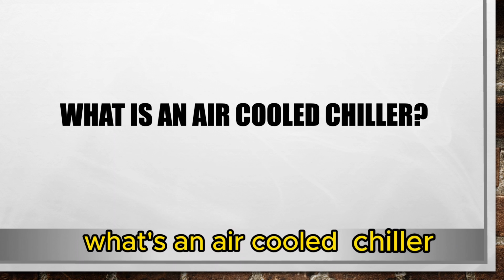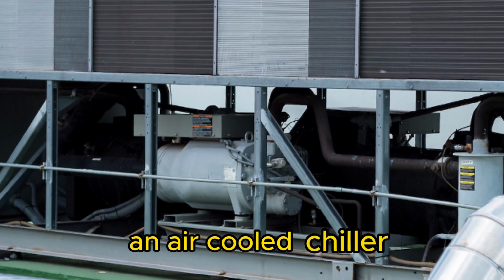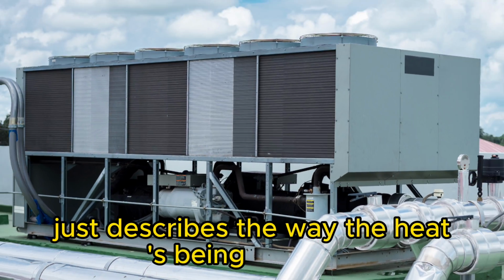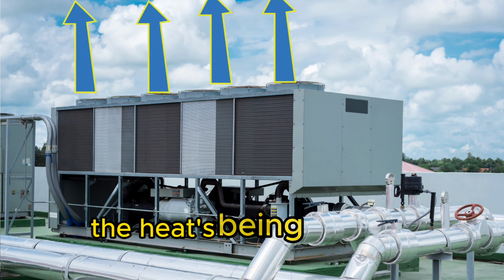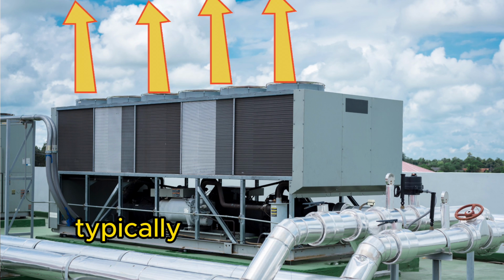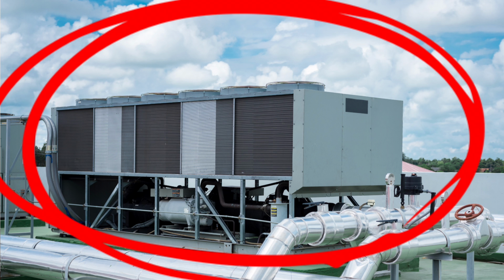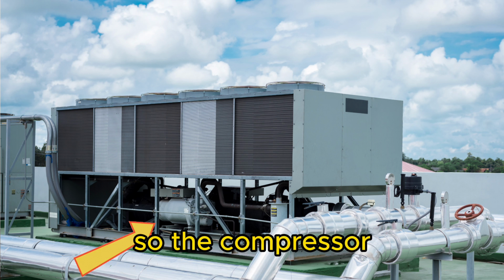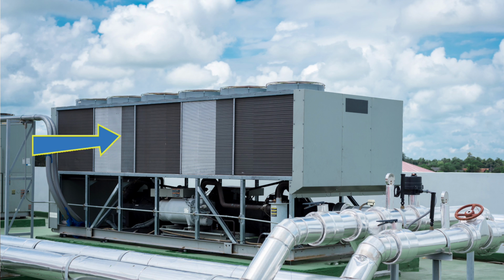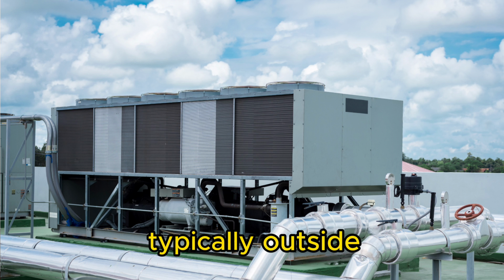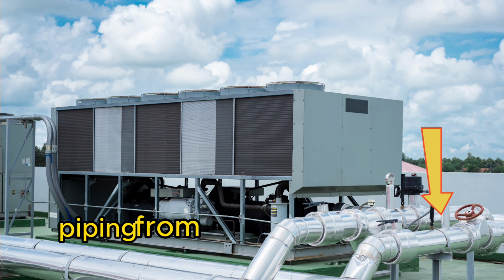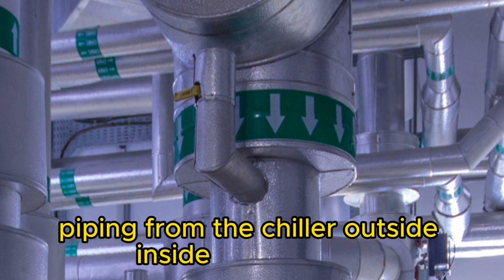What's an air-cooled chiller? Essentially, an air-cooled chiller just describes the way the heat's being rejected. In an air-cooled chiller, the heat's being rejected directly outside. Typically, you see air-cooled chillers as packaged units. So the compressor, evaporator, and condensing unit will be packaged in one, typically outside, and then they'll just run piping from the chiller outside into the building.